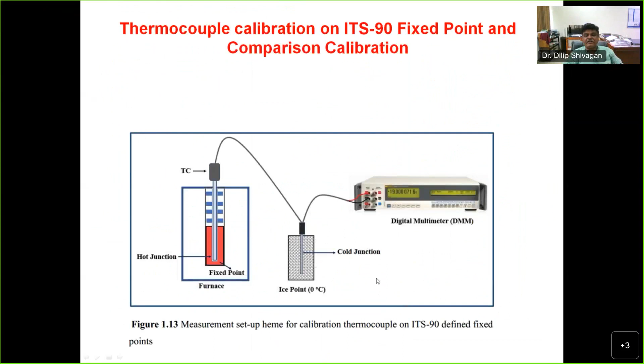So with immersion, there is little deviation, because the thermally migrated electrons from hot zones are coming to the cold zone. But they are not very linear. You can see in this case it is quite large. Because you see that furnace age, people are not using that very carefully, because they will put the thermometer at 1000 degrees Celsius in a very quick manner.